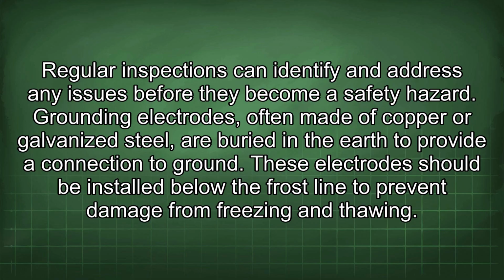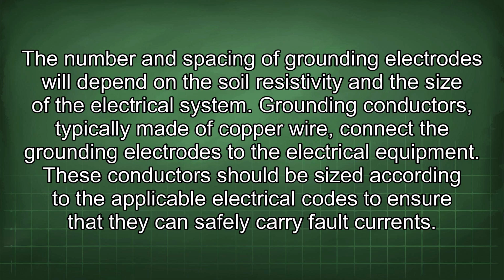Grounding electrodes, often made of copper or galvanized steel, are buried in the earth to provide a connection to ground. These electrodes should be installed below the frost line to prevent damage from freezing and thawing. The number and spacing of grounding electrodes will depend on the soil resistivity and the size of the electrical system. Grounding conductors, typically made of copper wire, connect the grounding electrodes to the electrical equipment. These conductors should be sized according to the applicable electrical codes to ensure that they can safely carry fault currents.